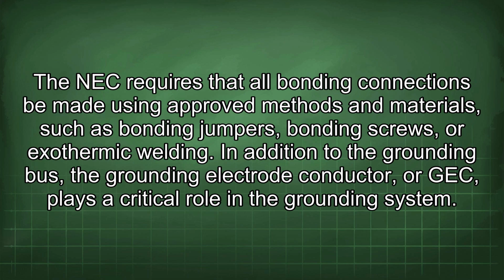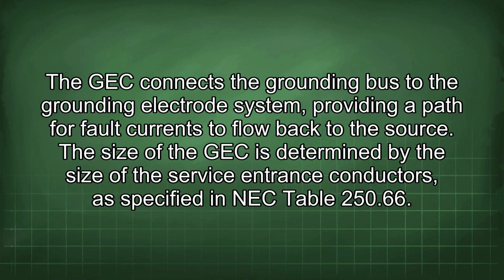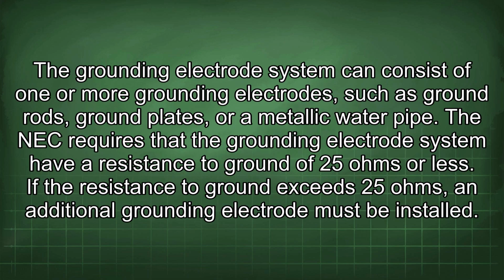or exothermic welding. In addition to the grounding bus, the grounding electrode conductor, or GEC, plays a critical role in the grounding system. The GEC connects the grounding bus to the grounding electrode system, providing a path for fault currents to flow back to the source. The size of the GEC is determined by the size of the service entrance conductors, as specified in NEC Table 250.66.